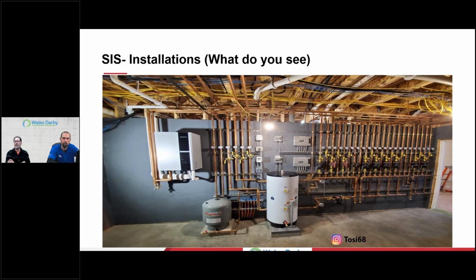But if you look at that magic box to the left, the line sets are down near the bottom. They go up to the roof and it looks like they go towards the back of the picture. And then the copper comes up and over and we do our, I guess it would be our primary secondary. I don't see it, I'd need to look right now. It should be, well, it's going to the buffer tank rather. That's what becomes primary secondary. The buffer tank becomes our separation from source to system.